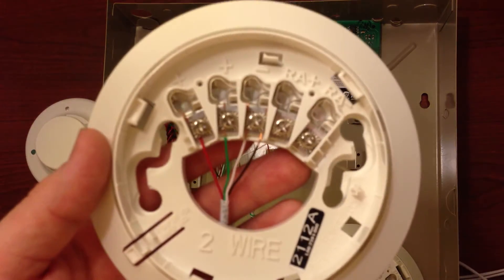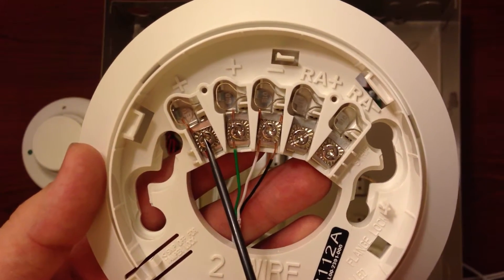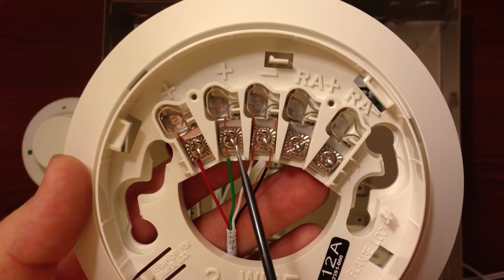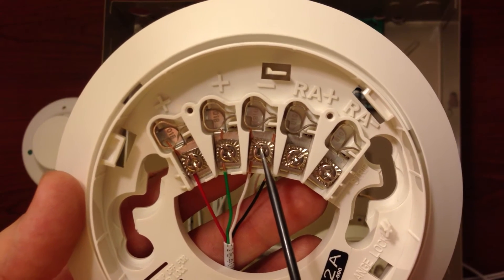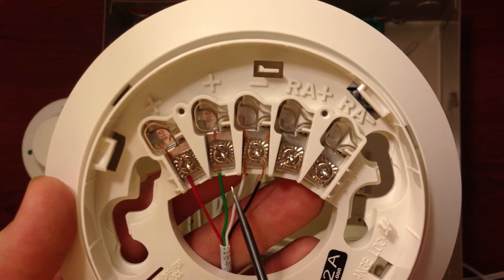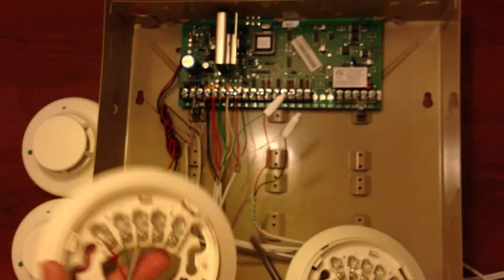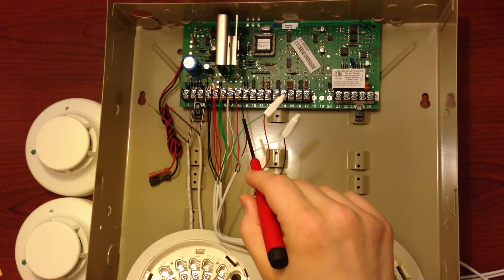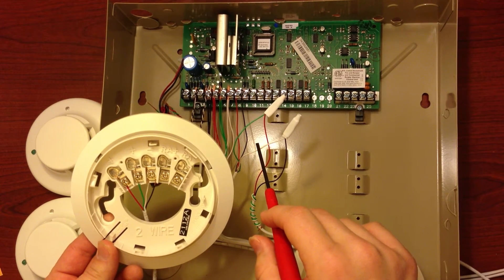Your first smoke detector in the line is going to look like this. Terminal 1 is the positive in, and terminal 3 is the negative in. To run the power on the outgoing feed, the positive out is terminal 2 and negative out is terminal 3. We'll utilize these two wires, your green and white, to run those back to the box, and then splice in the wire from the next smoke detector. The green wire was your positive out, and the white is your negative out from your first smoke detector.